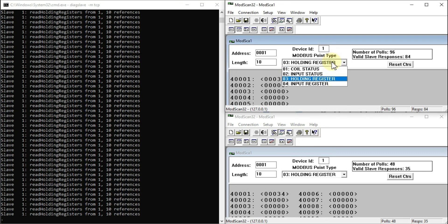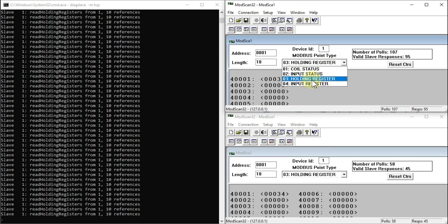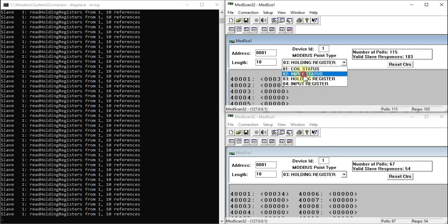This is how you can use the diagslave Modbus simulator to create your own local Modbus TCP server with all functionality like coil status, input status, holding register, and input register. If you use Modbus Slave software, you can only define one function code at a time — either holding register or input status — but with diagslave software you can define everything in one place.